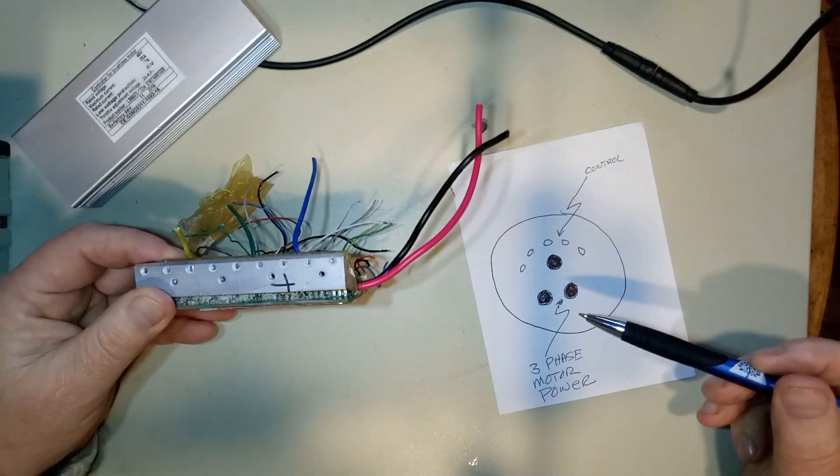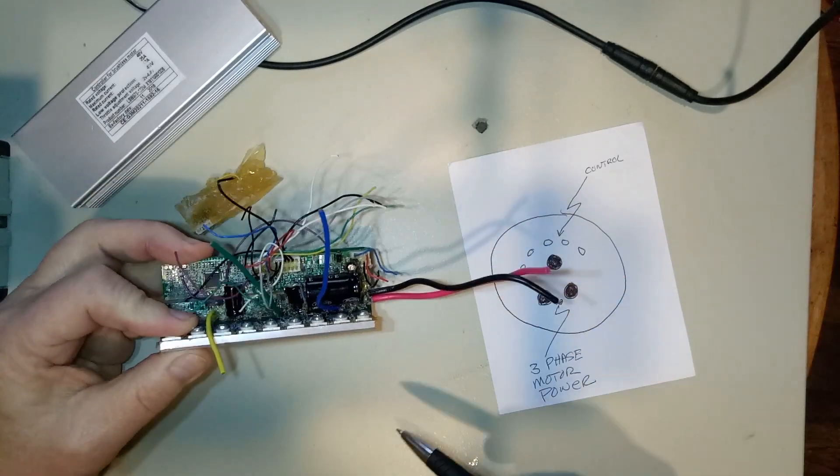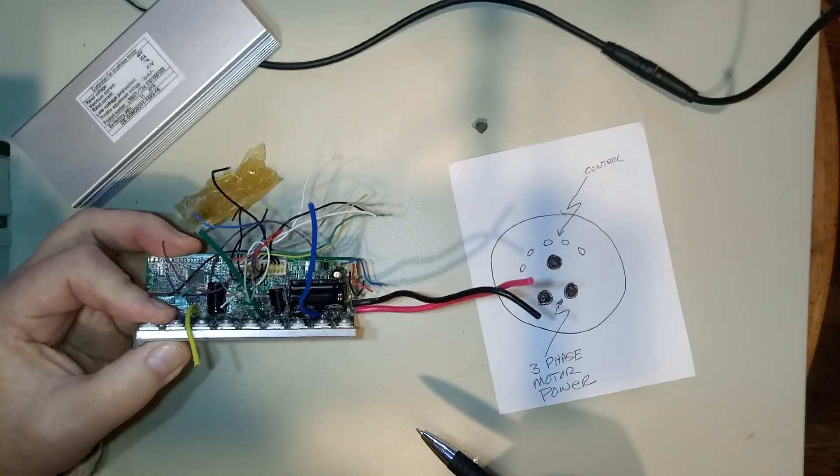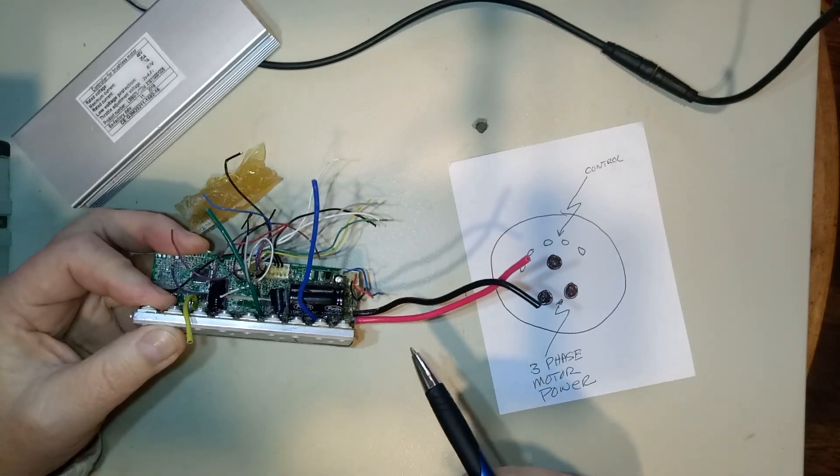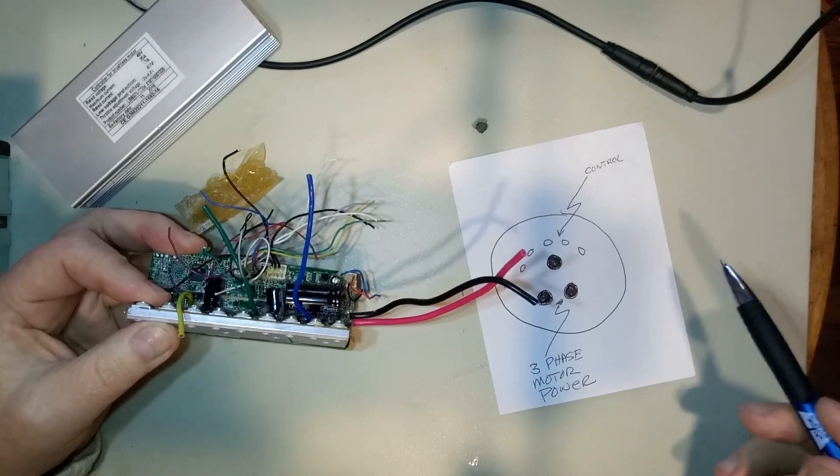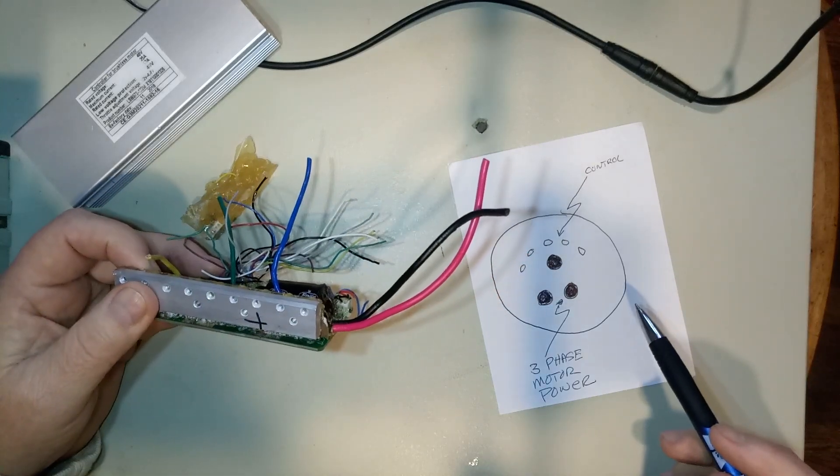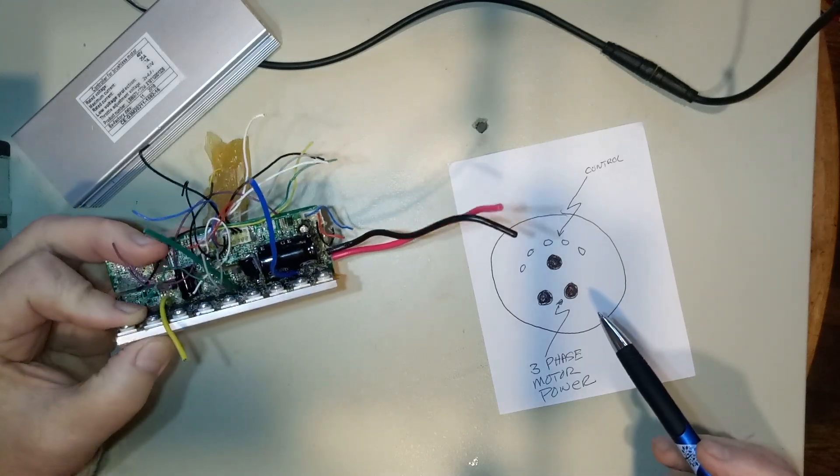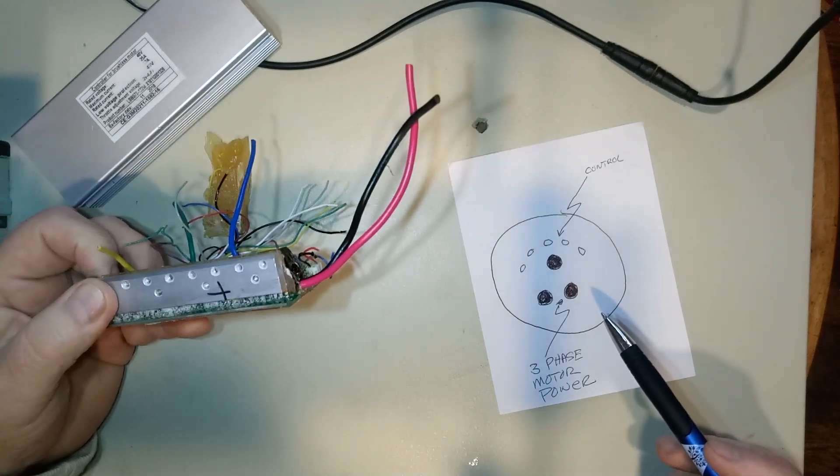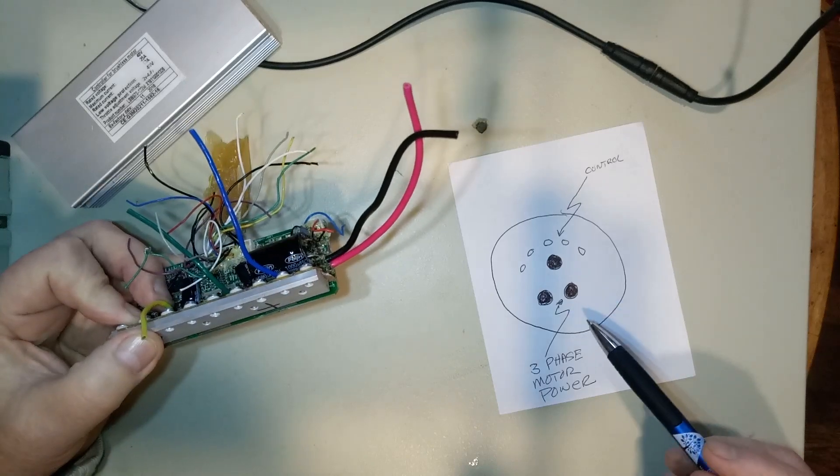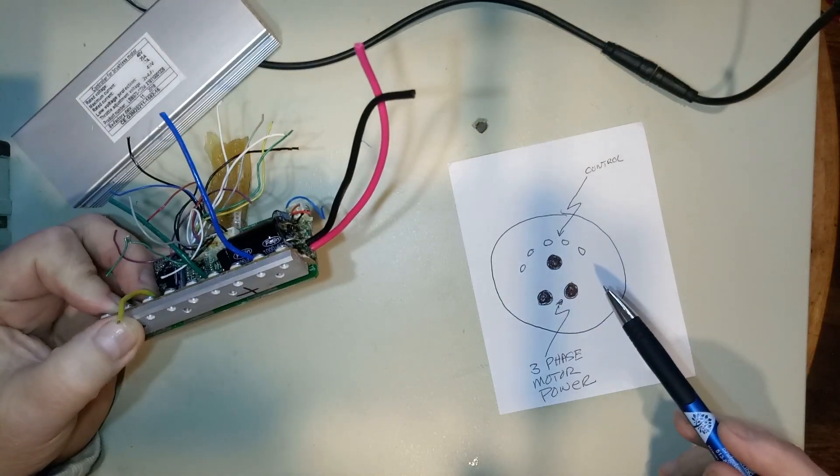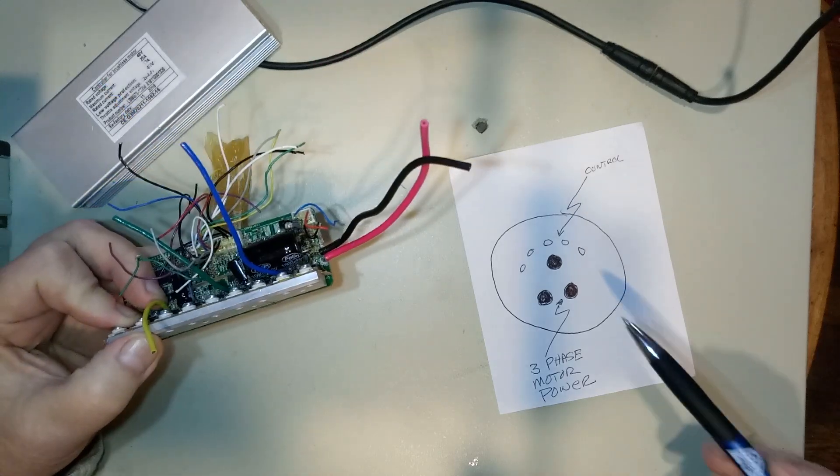This could have been fixed by carefully tearing into the wire and extending a loop over to the other connector, and it would work. But like I said, the guy put in a new one. It's working right now, but if this pin is bad and overheated, the other one's going to be bad, so it's going to fail at some point.